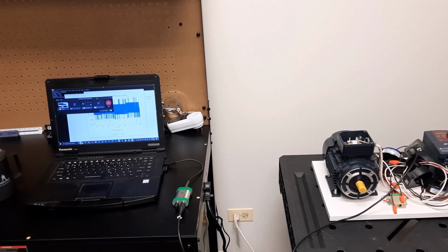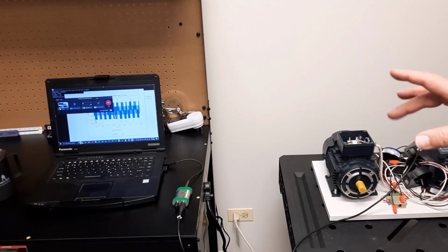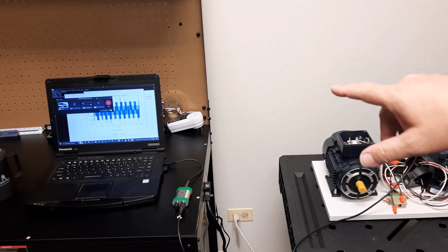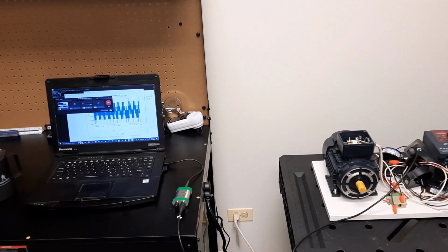First, we'll supply 240 volts. So it's going to be just over 180 volts. The machine and the software is not going to know that. Okay, so once we're there, you can see that there is some signal that occurs there. That's because whenever you have a drive supplied with power, there is some level of energy that is present all the time.